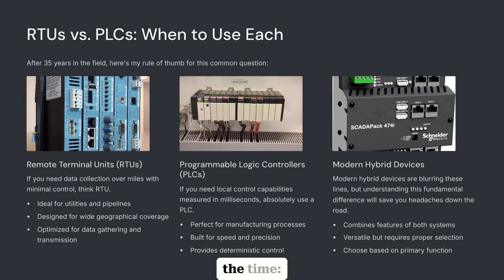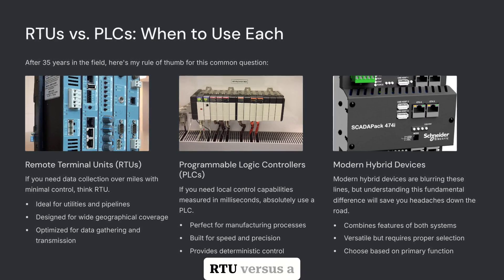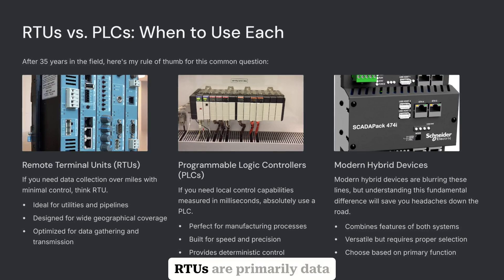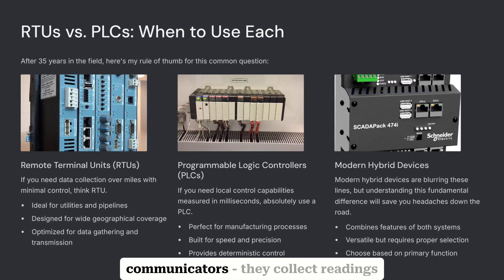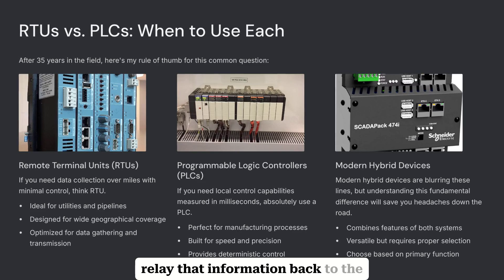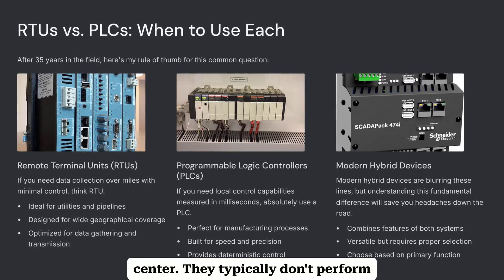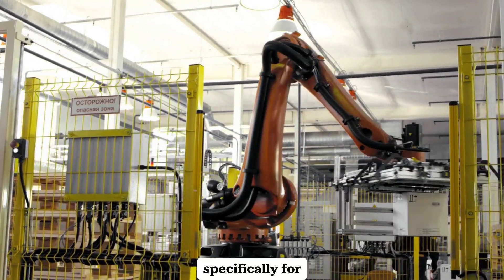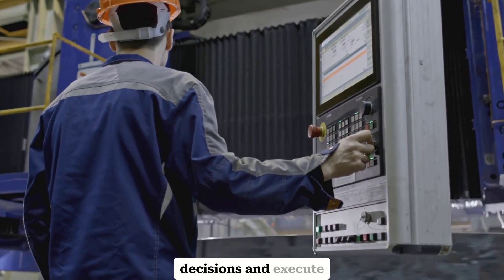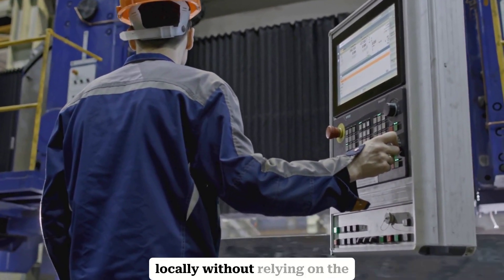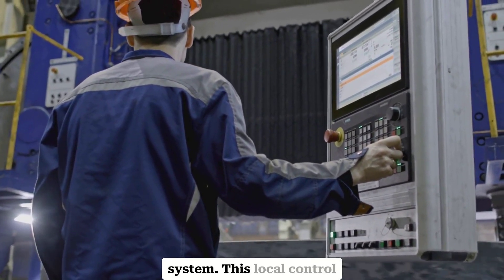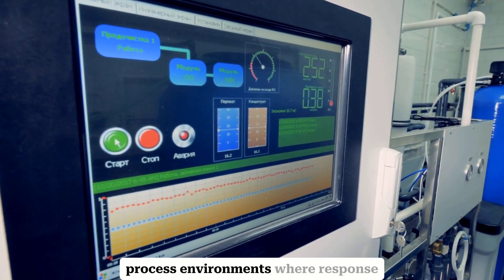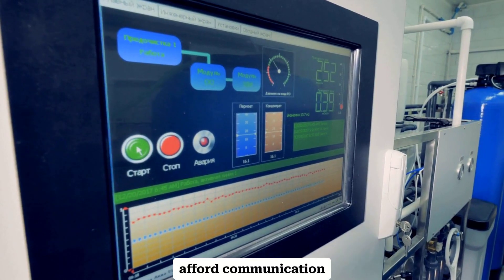A question I get all the time: when should I use an RTU versus a PLC? Here's the critical difference. Traditional RTUs are primarily data gatherers and communicators — they collect readings from field instruments and relay that information back to the control center. They typically don't perform local control functions. PLCs, on the other hand, are built specifically for control. They can make decisions and execute complex control logic locally without relying on the central system. This local control capability is absolutely essential in manufacturing and process environments where response time is critical and you can't afford communication delays.